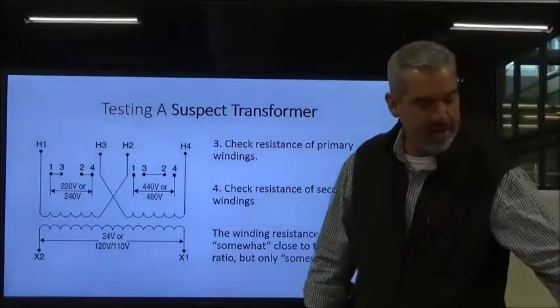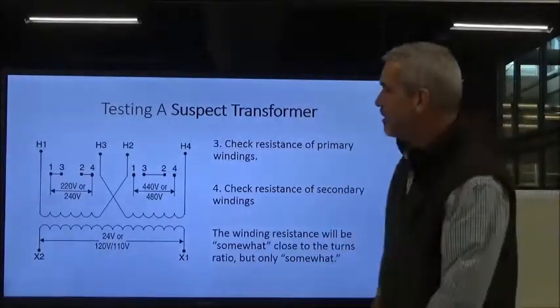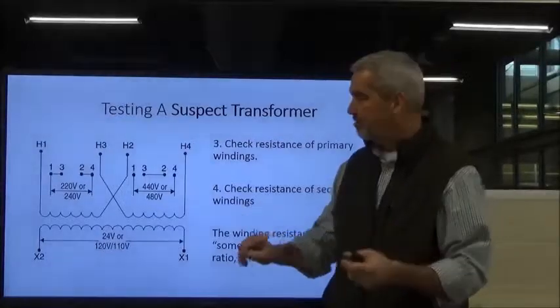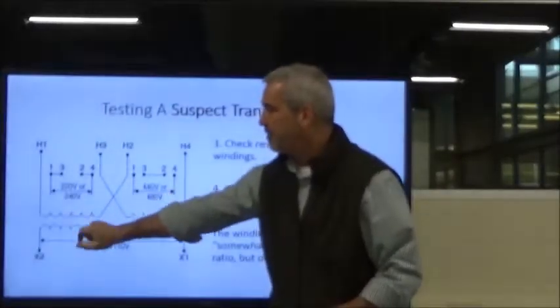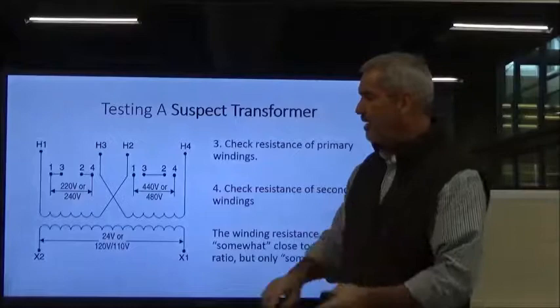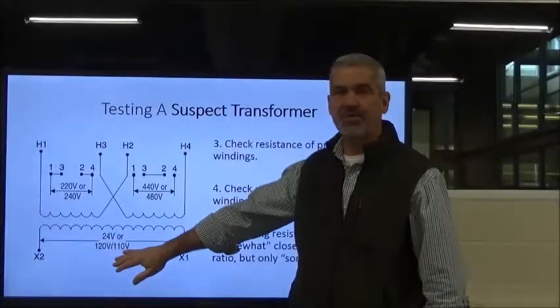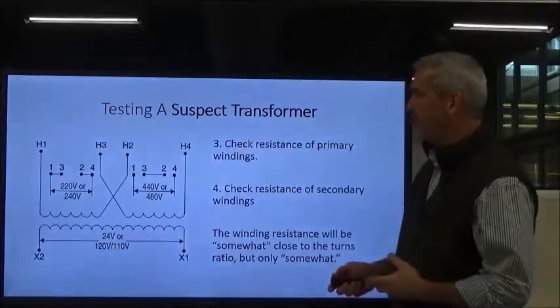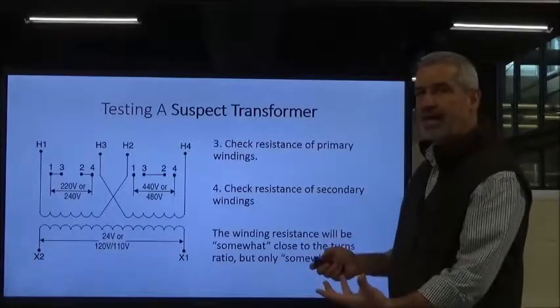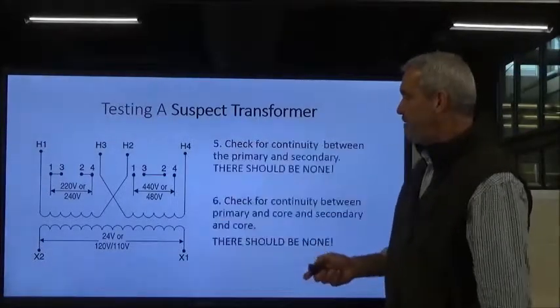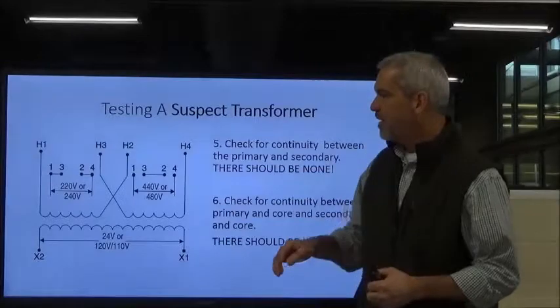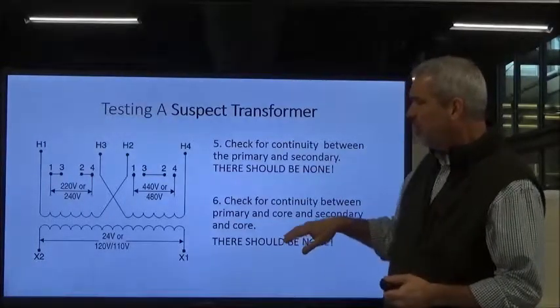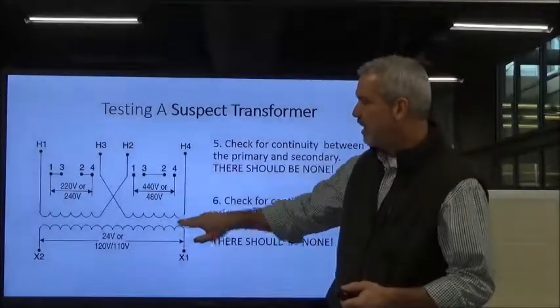So one way a transformer can fail is it can burn open, completely burning a gap in the windings, or it can short. It can happen on the primary side, and it can happen on the secondary side. So we want to check the windings on both sides with our ohmmeter. And the other way it can fail is that we could have continuity between these two coils.